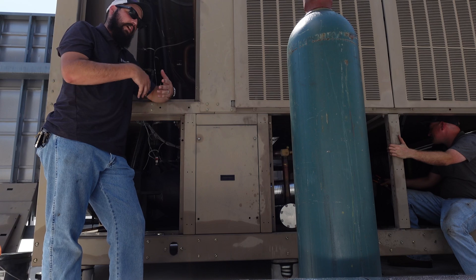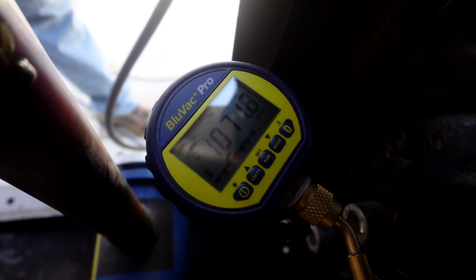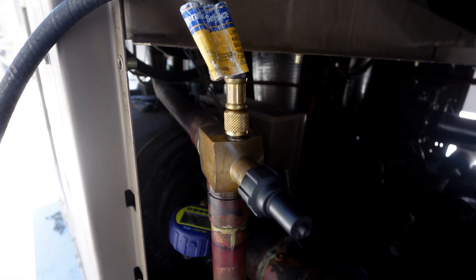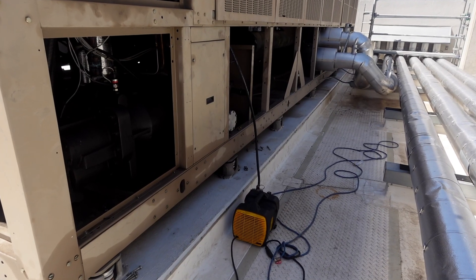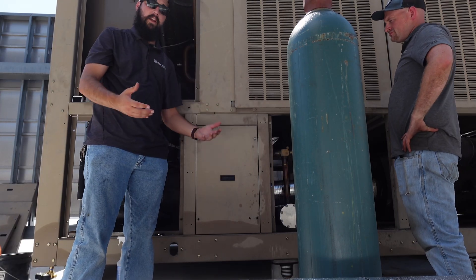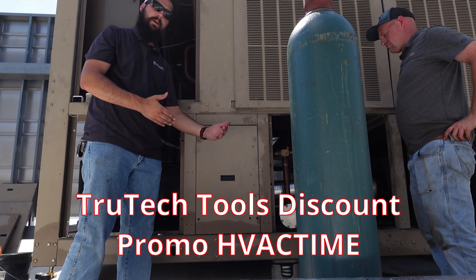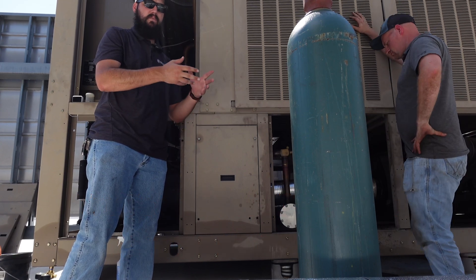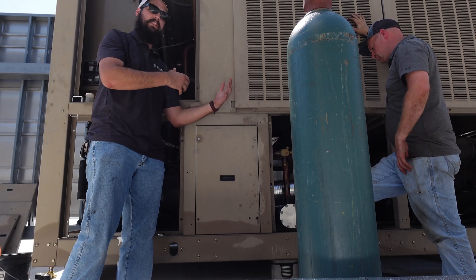This turned into two different leaks. We went through the process, pulled the vacuum — it got down to around 600 microns, then went to 680, then rose to 800-something within a couple of hours. We did a standing test just to see how it would do before doing anything, and stayed below 1,000 microns. Once we got it charged up, we put 120 pounds back in — we didn't charge the full weight, first in case we lost it, and second because undercharging would put more stress and heat on the whole system, which would help us identify the problem faster.